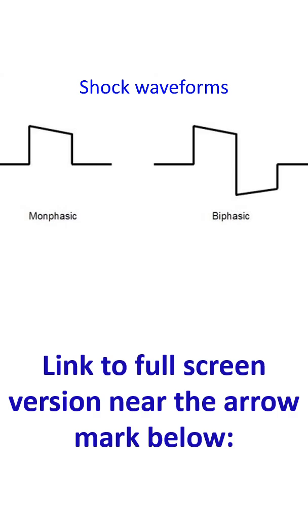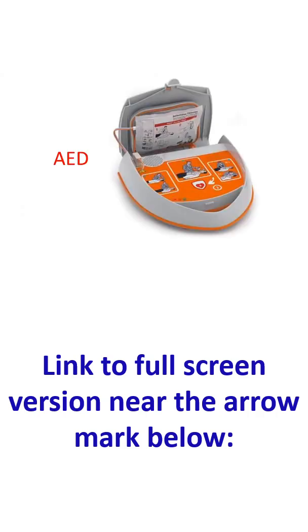The energy used in a biphasic device is 150 to 200 joules, while that in a monophasic device could be as high as 360 joules. Biphasic devices are more efficient than monophasic devices, which are being phased out. What are the other special types of defibrillators?